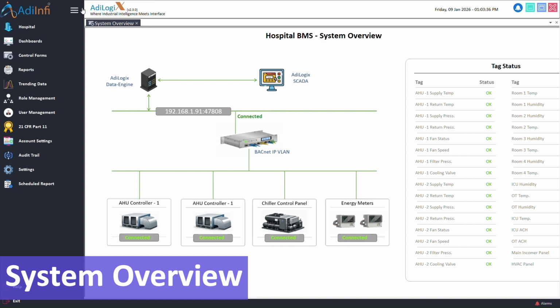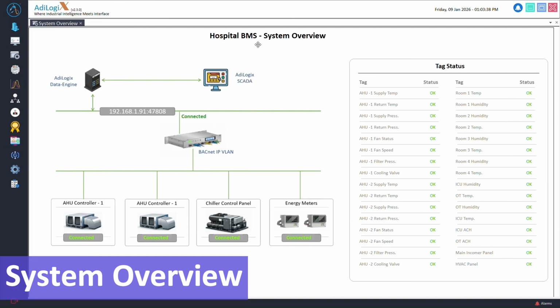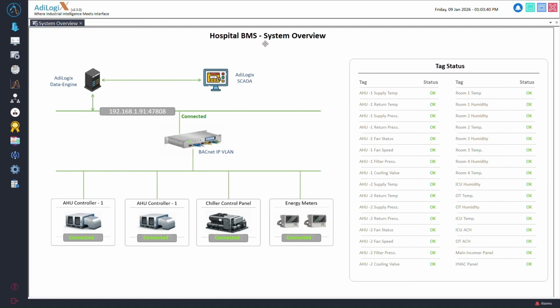This system overview illustrates how AdiLogiX connects field devices, control systems, and operators into a single, secure architecture. At the core is the AdiLogiX data engine responsible for device communication, data normalization, and real-time processing. AdiLogiX communicates with building devices over an industrial Ethernet network using BACnet IP. Every connection is actively monitored, ensuring visibility, reliability, and rapid fault detection.